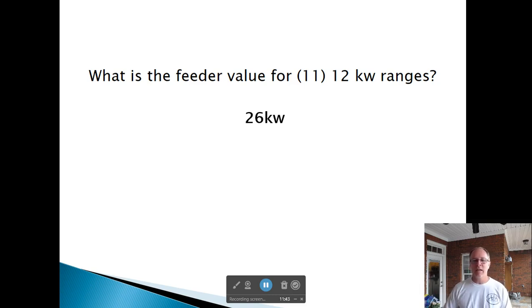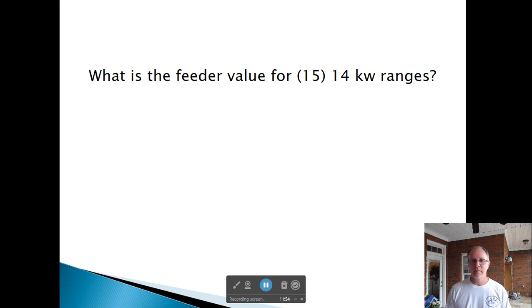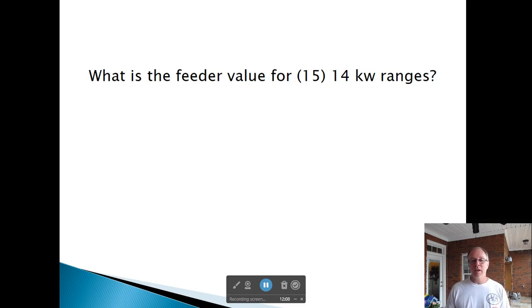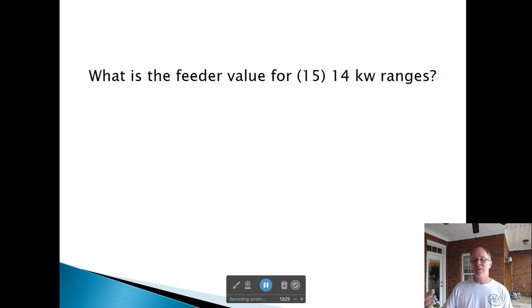If it's a little more than 12 kW, you add 5% per kW above 12. What is the feeder value for 15, 14 kW ranges? 15 appliances in Column C is 30 kW. Since it's 14 kW — 2 kW over 12 — we add 10%. So 30 times 1.10 gives 33 kW.